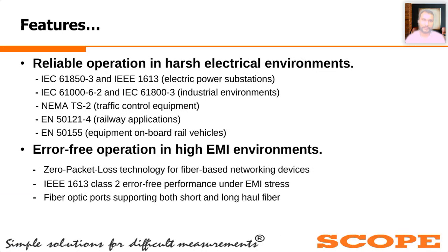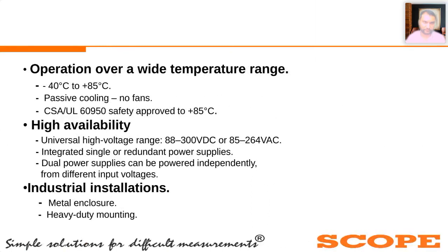Reliable operation in a harsh electrical environment, per these IEC regulations. Error-free operation in a high EMI environment, like zero packet loss technology, error-free performance under EMI stress. It supports all these key features. Temperature, as I said, it can operate from minus 40 degrees to plus 85 degrees centigrade. Highly available.